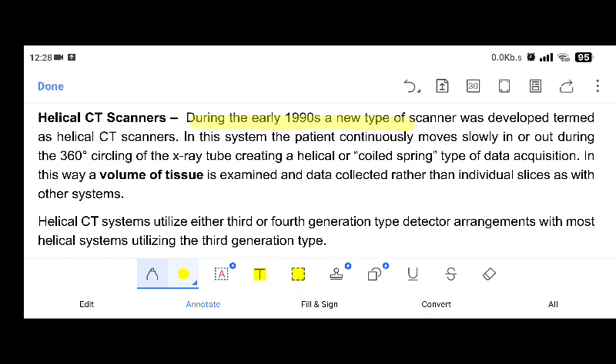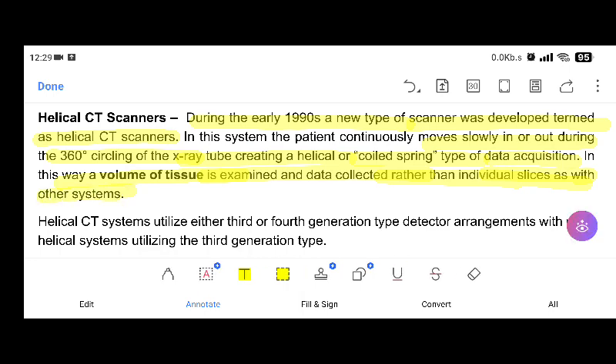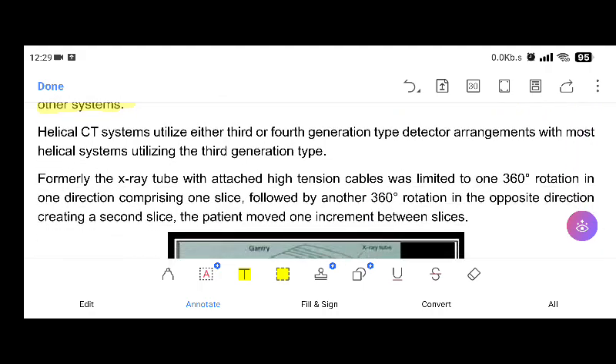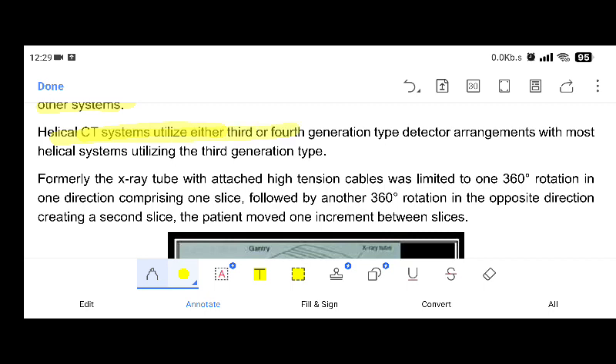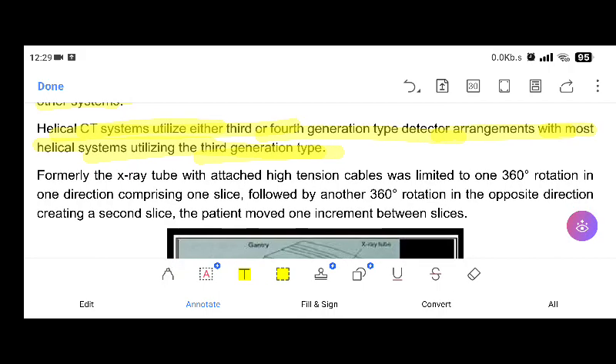So during the early 1990s, a new type of scanner was developed known as the helical CT scanner. In this system, the patient continuously moves slowly in or out during the 360-degree circling of the X-ray tube, creating a helical or coiled spring type of data acquisition, where a volume of tissue is examined and data collected rather than individual slices as with other systems. Helical CT systems utilize either third or fourth generation type detector arrangements, with most helical systems utilizing the third generation type.